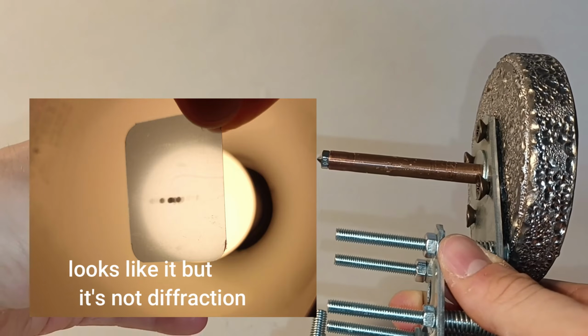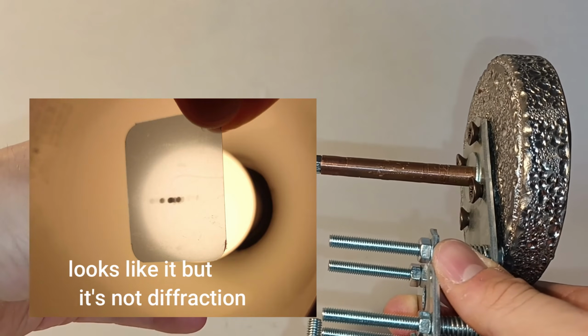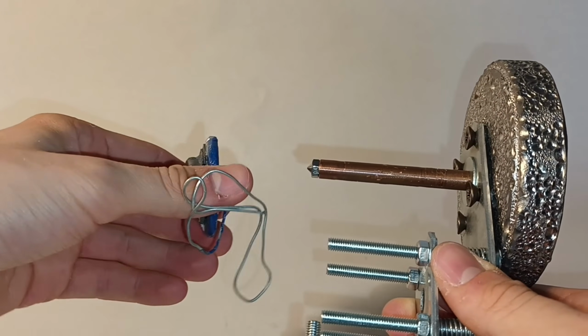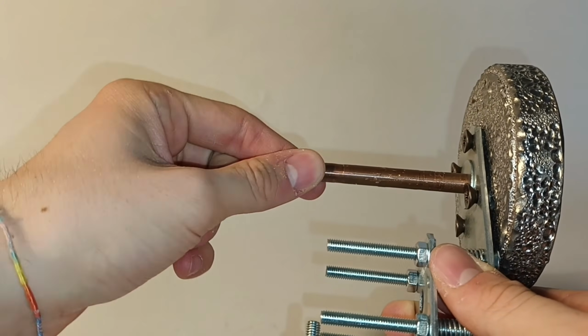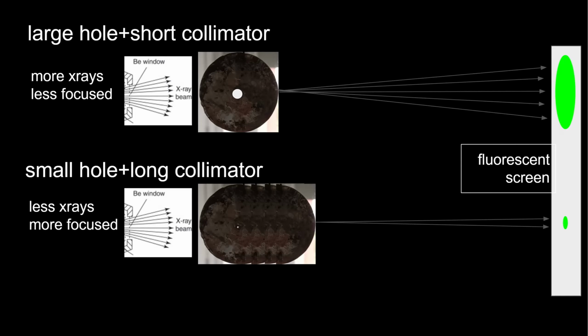Also, the length of the collimator is inversely proportional to the dispersion of the X-ray beam output from the exit of the collimator. So in simple terms, it means that if we have a large hole and a short collimator, like the first prototype that I've made, we get at a fixed distance a large cloud of X-rays, as you can see on the fluorescent screen on the right.